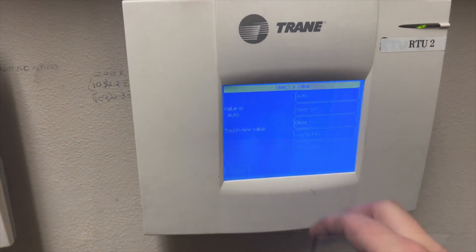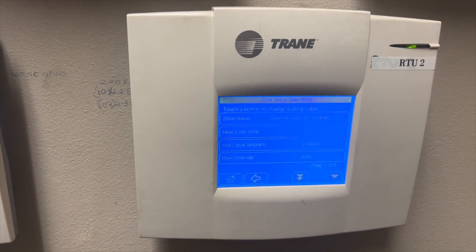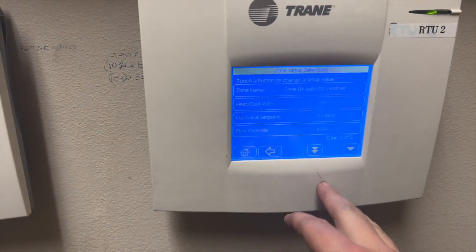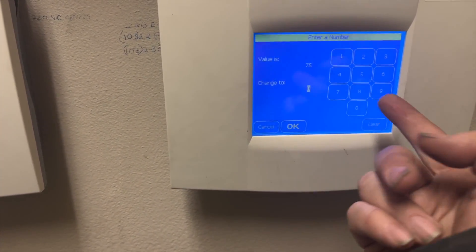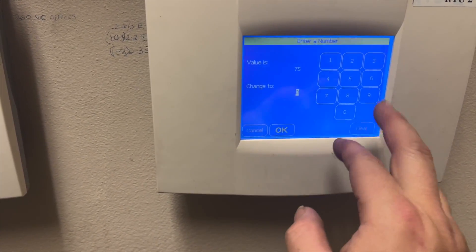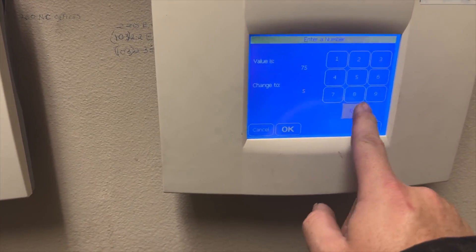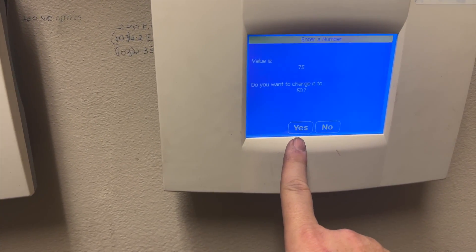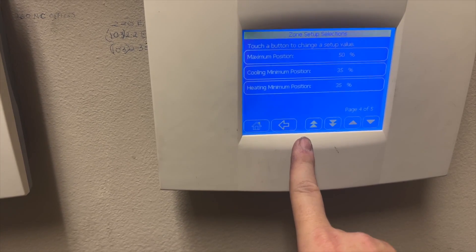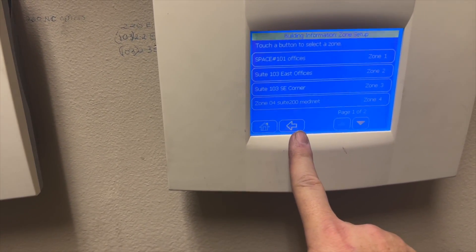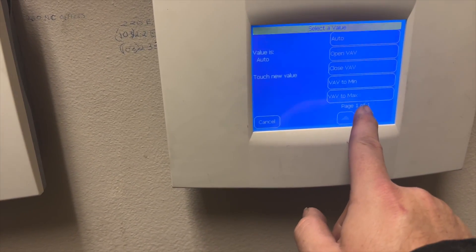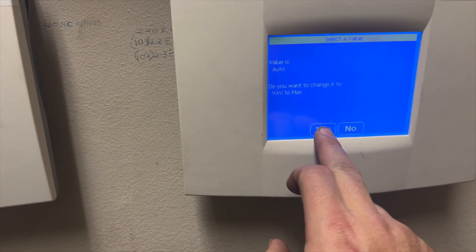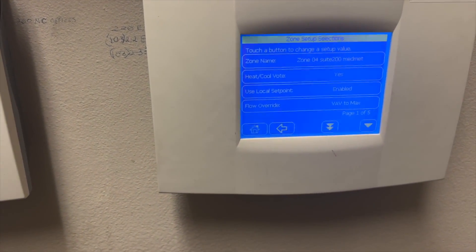It looks like we just need to change our maximum setting and lower it a little bit. We'll go ahead and put it back into auto. Now we need to see if we can change the settings. Our maximum is 75, which is way too much — let's try 50. Then we'll run it at maximum to see how loud it is. We need to go back to Flow Override and go to VAV to max, which should put us at 50 percent.